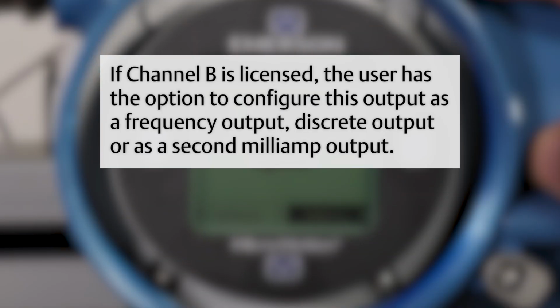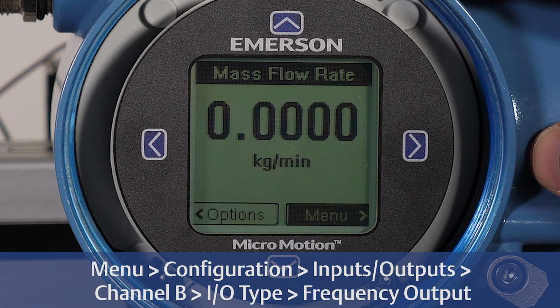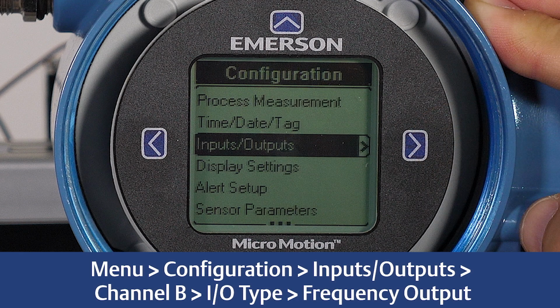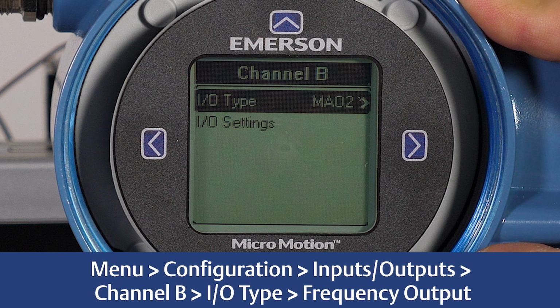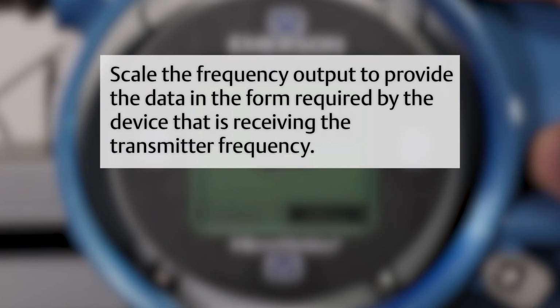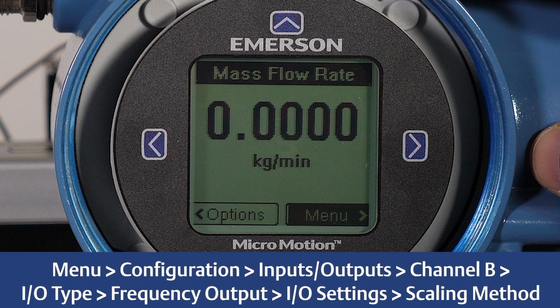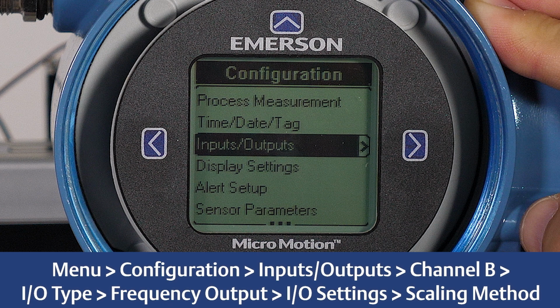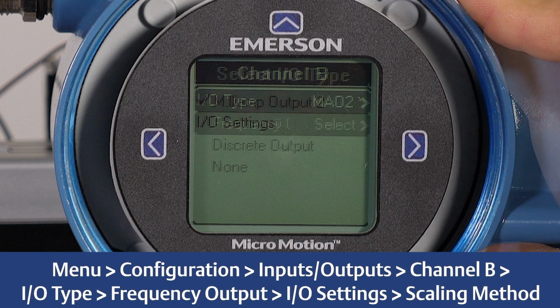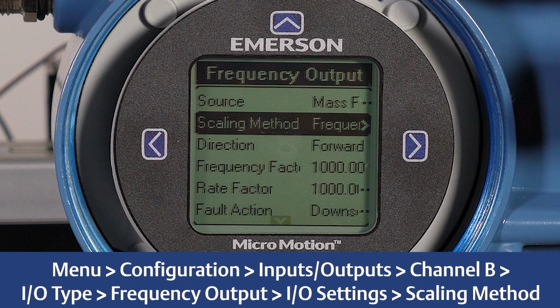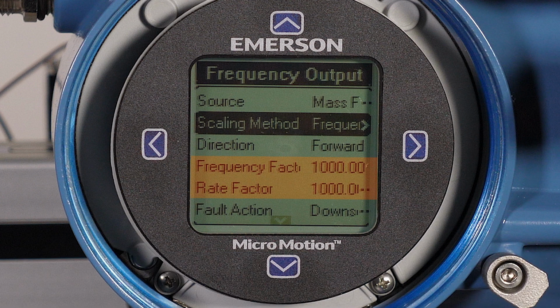If Channel B is licensed, the user has the option to configure this output as a frequency output, discrete output, or as a second milliamp output. Using the display, select Menu, Configuration, Inputs, Outputs, Channel B, I/O Type, Frequency Output. Scale the frequency output to provide the data in the form required by the device that is receiving the transmitter frequency. This can be completed by using the display and selecting Menu, Configuration, Inputs, Outputs, Channel B, I/O Type, Frequency Output, I/O Settings, Scaling Method. The frequency factor and rate factor can also be configured in this menu, along with the source of the frequency output.